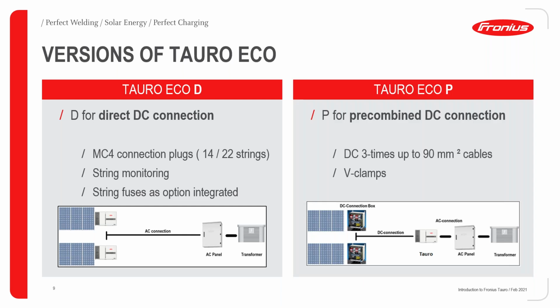Then the pre-combined version, Tauro Eco P, we call pre-combined. These versions are used for more centralized topology. Centralized means you want to put the PV panels in a separate place, and then you will bring all the DC cables to the place where all the inverters are placed in a centralized way, near the AC panel or transformers. This version of the inverter has DC space for the DC cable, because normally you will use a DC connection box to bring the strings together, and then you can bring the DC cable to the inverter, 3 times up to 90 square millimeter. And there is a space inside the inverter with V clamps where you can connect these combined DC strings.